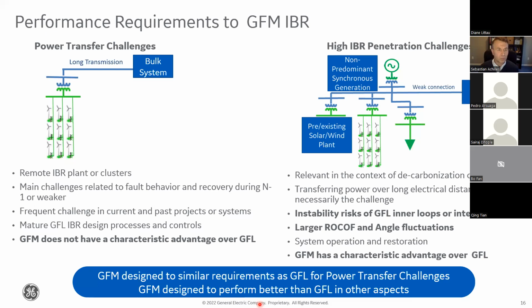With the system on the left, there is grid following inverter technology that has been designed to operate with problems like this for many years, like Pedro was describing. Some grid following performs very well in this, and some other grid following may not perform as well. It depends on how they're designed and the particular interest of the OEM. Now, in these systems, there is an intrinsic limitation of the transmission line on how much power you can get out of the inverter-based resource plant. It doesn't matter if you have a grid following plant, a grid forming plant, or a synchronous machine, that limitation exists. And the grid forming features in a wind plant or a solar plant are not necessarily going to overcome that. So there are limitations intrinsic to the long transmission system.